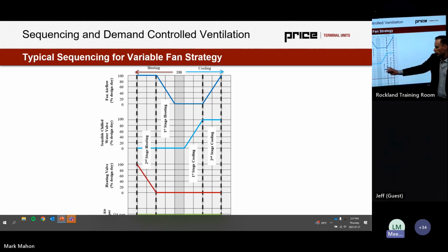That's why we do hydronics first for cooling, although there could be some staging where they both vary just at different slopes and outpace one another. When we move towards the second stage of heating, that's where we pull in our electric coil or our hot water coil or whatever else we may need. Perimeter reheat from other fin tubes, there's lots of options. But generally, this is the kind of relationship we see, which is a little counterintuitive, so I like to point that out.